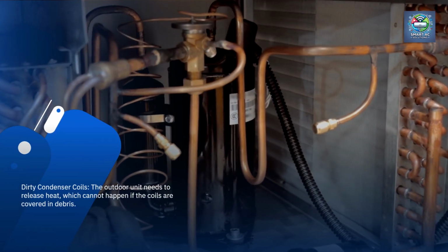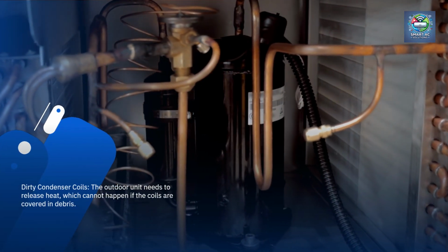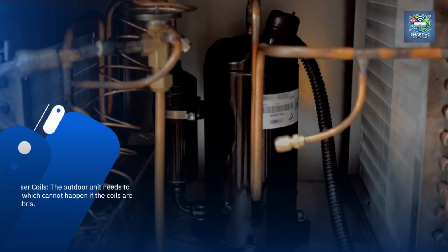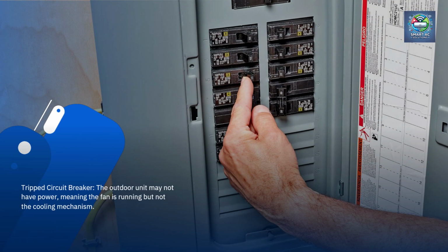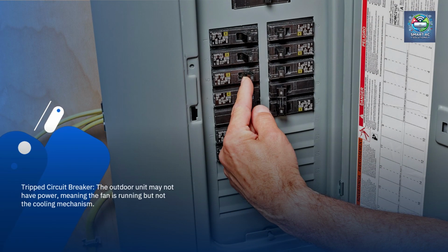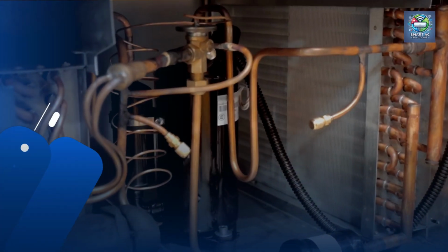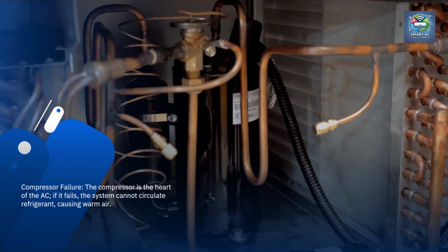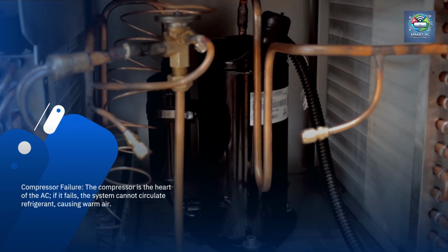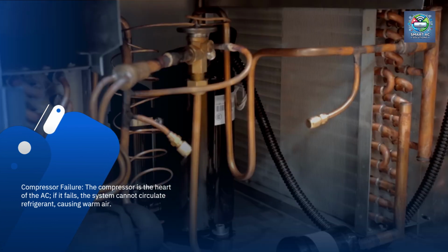Dirty condenser coils. The outdoor unit needs to release heat, which cannot happen if the coils are covered in debris. Tripped circuit breaker. The outdoor unit may not have power, meaning the fan is running but not the cooling mechanism. Compressor failure. The compressor is the heart of the AC. If it fails, the system cannot circulate refrigerant, causing warm air.